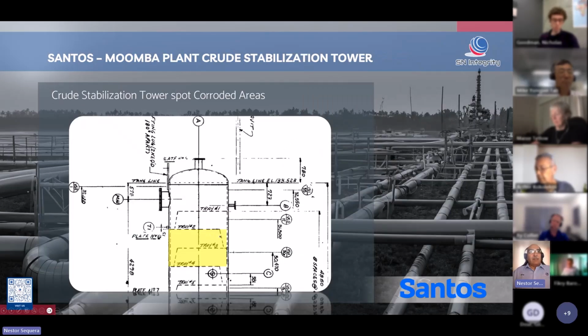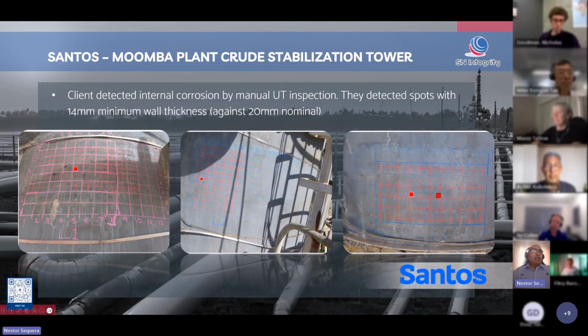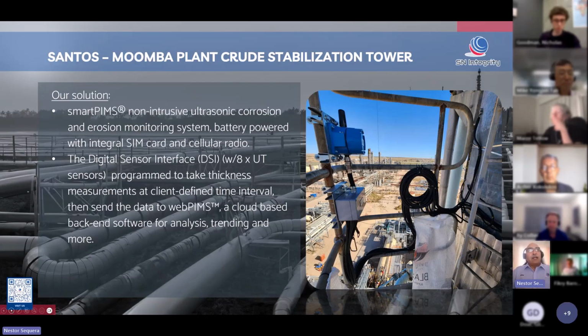The area where the damage was located was, as I said, at the top between train 2 and train 4. They mapped that area using phased array and gridded the area, found the lowest points and nominated those to install our sensors. So we got contacted, and within a week we set up one of our SmartPIMS units, which is the blue box on the right picture there, a corrosion erosion monitoring system powered by batteries that can be fitted with a radio module with a SIM card that can send data straight away to the cloud-based software for corrosion rate calculation, alerts and so on.